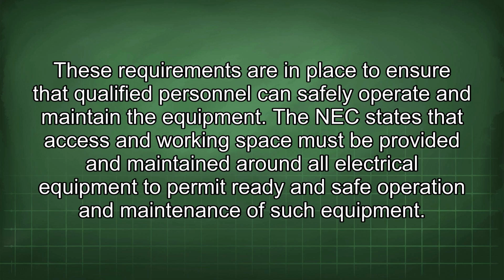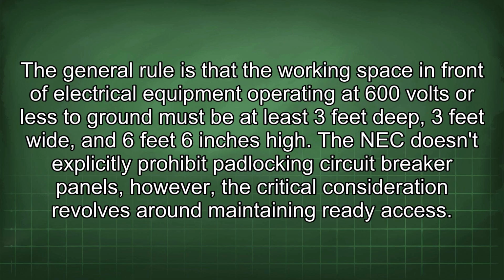The NEC states that access and working space must be provided and maintained around all electrical equipment to permit ready and safe operation and maintenance. The general rule is that the working space in front of electrical equipment operating at 600 volts or less to ground must be at least 3 feet deep, 3 feet wide, and 6 feet 6 inches high.